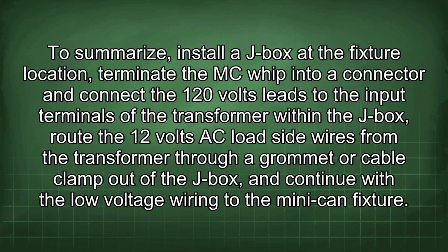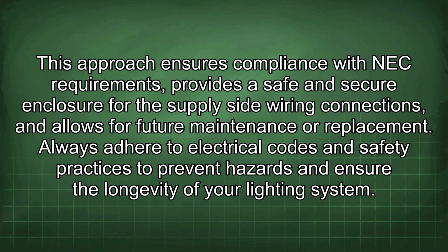To summarize, install a J-box at the fixture location, terminate the MC whip into a connector and connect the 120 volts leads to the input terminals of the transformer within the J-box. Route the 12 volts AC load side wires from the transformer through a grommet or cable clamp out of the J-box and continue with the low voltage wiring to the mini-can fixture. This approach ensures compliance with NEC requirements, provides a safe and secure enclosure for the supply side wiring connections, and allows for future maintenance or replacement. Always adhere to electrical codes and safety practices to prevent hazards and ensure the longevity of your lighting system.